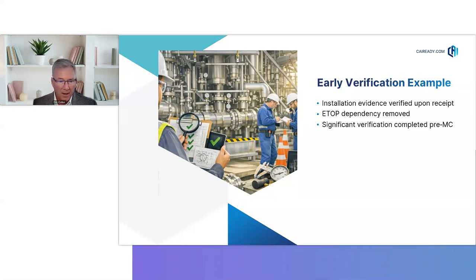What's important here isn't vendor calibration certificates, weld records, or material certs individually. It's what they represent. Stick-built systems like WFI loops are full of verification activities that are independent of overall system completion. When these activities are delayed, C&Q is artificially pushed onto the critical path. Identifying and executing these verifications as soon as the evidence exists is one of the fastest, lowest risk ways to pull C&Q left without increasing regulatory risk and without increasing validation effort.